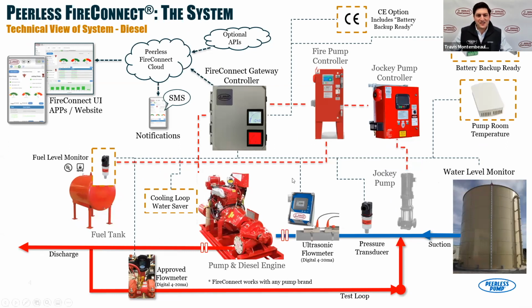But this slide really shows what you would see within a fire pump room itself. So you see your diesel engine and your fire pump here. So Drew, you had your diesel engine picture. On the back side of that is the pump. In this case here, we've got the pump. That's always connected to a main fire pump controller, so a diesel or an electric driven controller. You've got a jockey pump system, so for your daily pressure maintenance, so your fire pump's not turning on and off, day in and day out. You've got that jockey pump there.